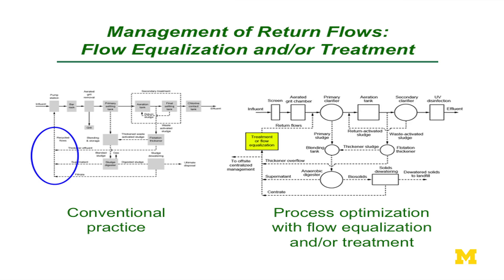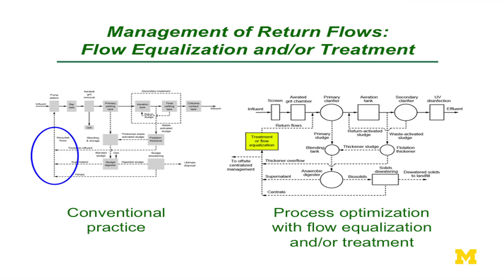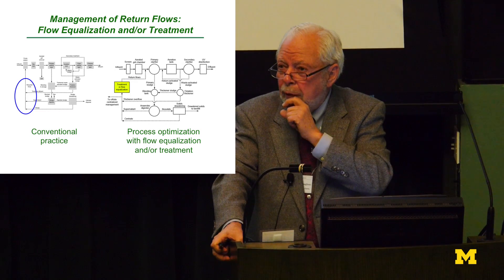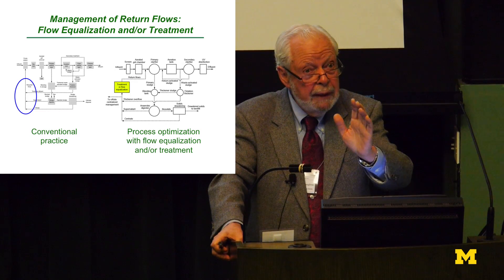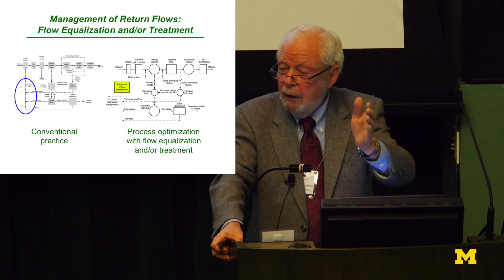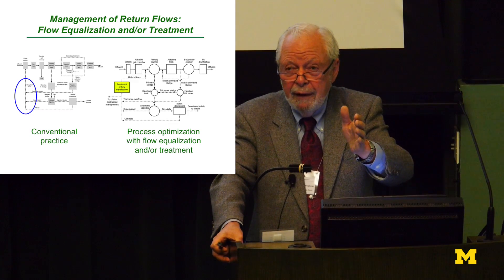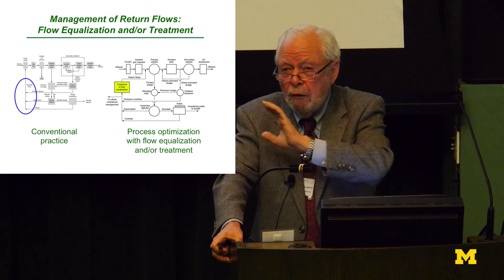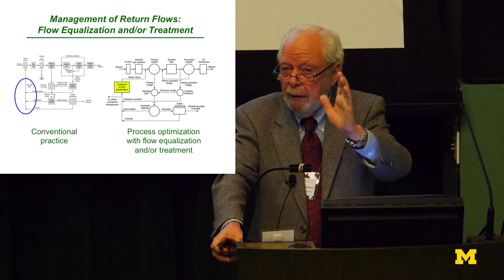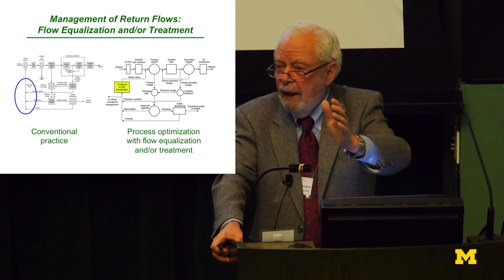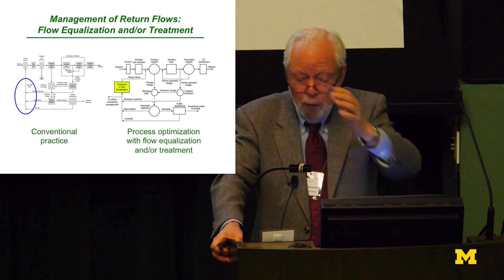The conventional diagram shows all return flows brought back to the headworks. You talk to operators and ask when they return their flows — and they say the operators are here during daytime hours, so the flows come back during daytime when you have peak organic loading — then you wonder why the treatment plant doesn't work. As a minimum, all those flows should be captured and brought into the plant from 8 to 6 in the morning because you've got excess aeration capacity. Coupling that with load equalization changes things even more dramatically.